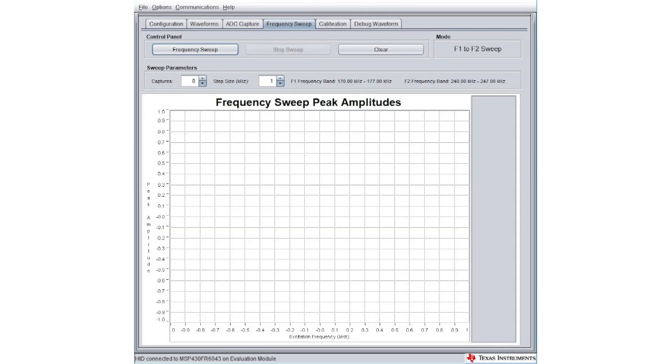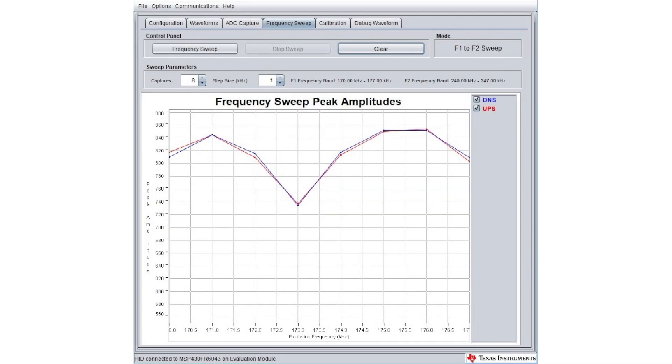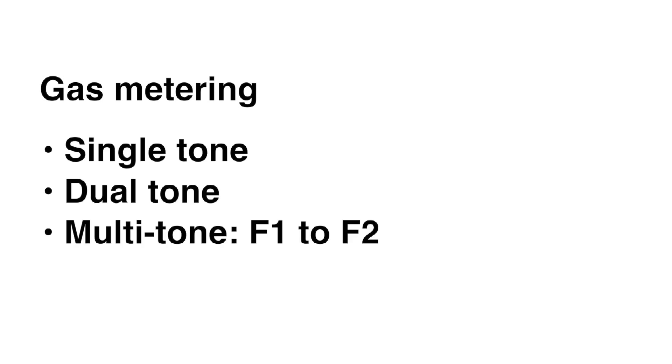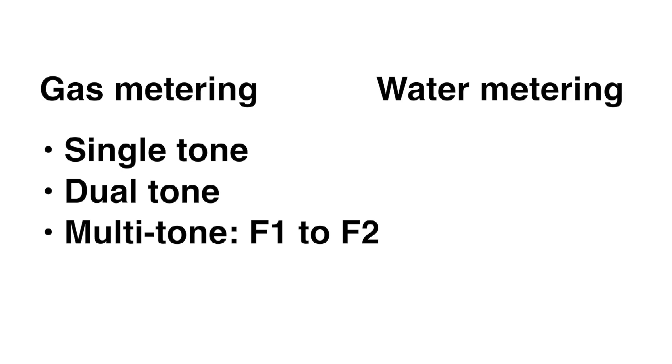The Frequency Sweep tab enables you to find the optimal frequency based on your selected transducer with the highest amplitude. For gas metering, we support three pulse modes: single tone, dual tone, and F1 to F2 sweep. For water metering, we only support single tone.